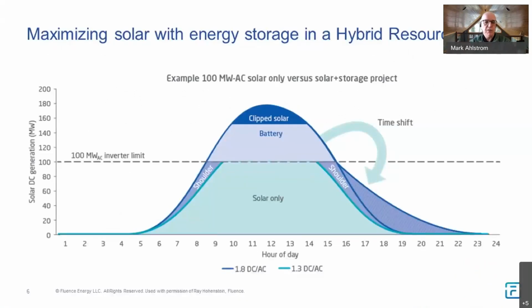This was alluded to as well in terms of what Andrew was talking about with the DC coupled design with the higher inverter loading ratio, or I call it here the DC-AC ratio. If you do an optimized standalone PV plant today, shown as the lighter green at the bottom, it optimizes out, so a 100 megawatt PV plant would typically have about 130 megawatts of PV panels to make up for losses and less sunny days and so forth.